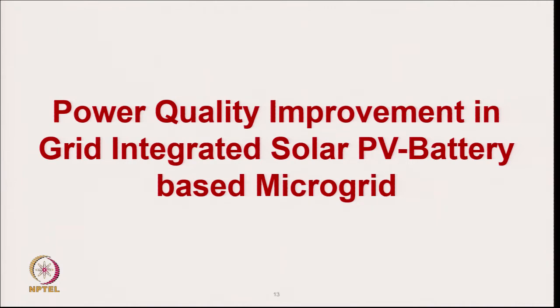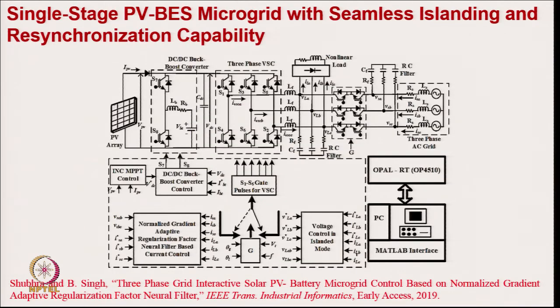Coming to power quality improvement in grid-integrated solar PV based microgrid with a typical single-stage PV based microgrid system. We have a solar PV array with a single stage and a buck-boost converter for the battery. This buck-boost converter allows maximum power tracking by controlling the DC link voltage, so one converter can be eliminated and the battery voltage can be at optimum voltage. Under unbalanced load conditions, second harmonics in the DC link are prevented from flowing into the battery. The total system can be synchronized to the grid when grid is available and provide power to the local load, which may include linear and non-linear loads.